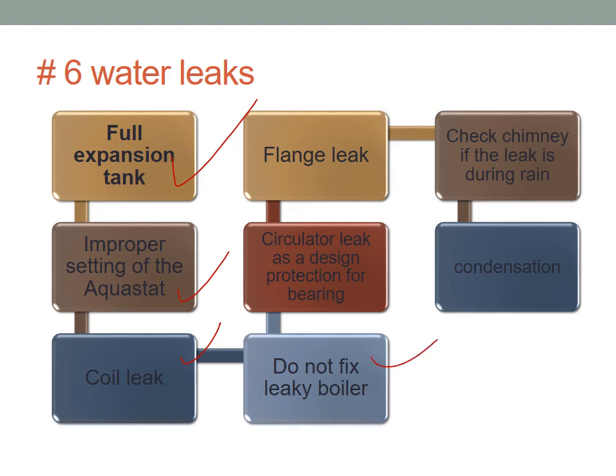Do not fix a leaky boiler. That's an issue. So we don't want to fix a leaky boiler. We want to always replace them. It's not fixed. Do not use ceramics or glue or whatever. It has to be replaced.